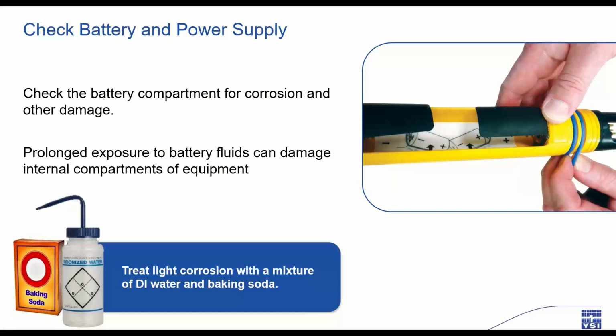Unless you submerge your equipment without the battery cover or port plugs, you should really have no electrical component issues from water. If we do see this type of damage, it is usually caused from battery leakage. Alkaline batteries can leak fluid that is harmful to the internal components of a sonde. Sondes that have been exposed to these types of fluids for longer periods of time will likely have corroded contacts and need to be sent to service centers for repairs.